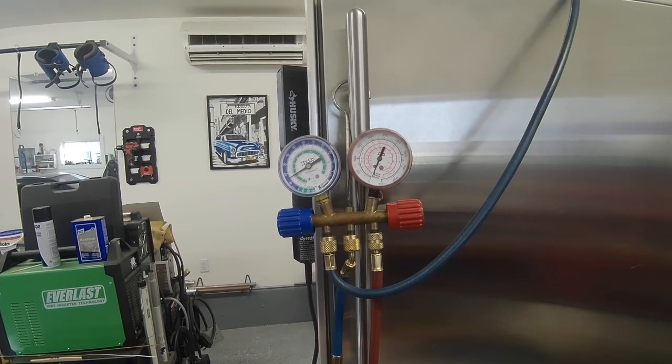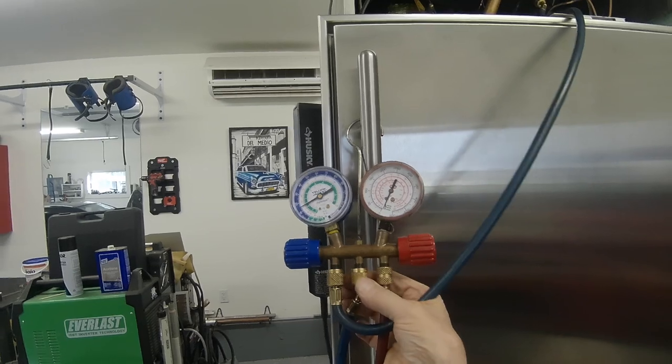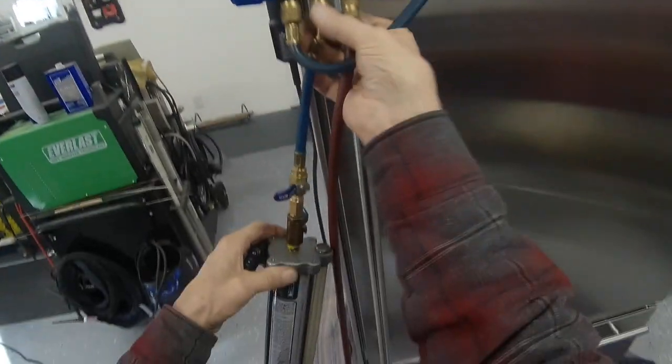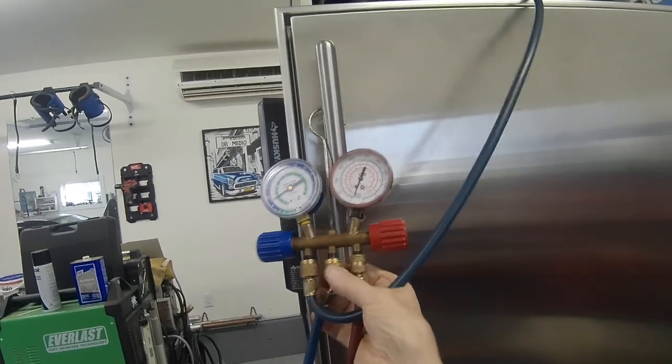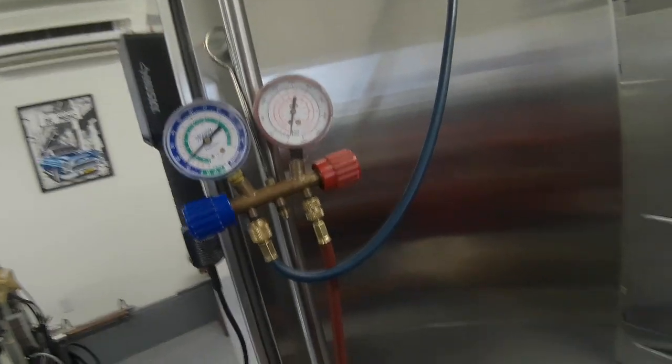The back pressure is approximately 15 psi, which is good. Anywhere between 12 and 15, I like it. Wait for it to shut off. Finish putting it back together and it will be done.